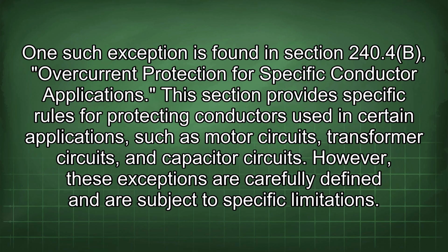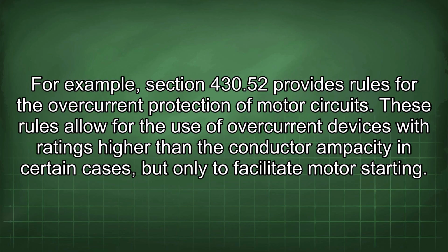One such exception is found in Section 240.4(B), Overcurrent Protection for Specific Conductor Applications. This section provides specific rules for protecting conductors used in certain applications, such as motor circuits, transformer circuits, and capacitor circuits. However, these exceptions are carefully defined and are subject to specific limitations. For example, Section 430.52 provides rules for the overcurrent protection of motor circuits. These rules allow for the use of overcurrent devices with ratings higher than the conductor ampacity in certain cases, but only to facilitate motor starting.